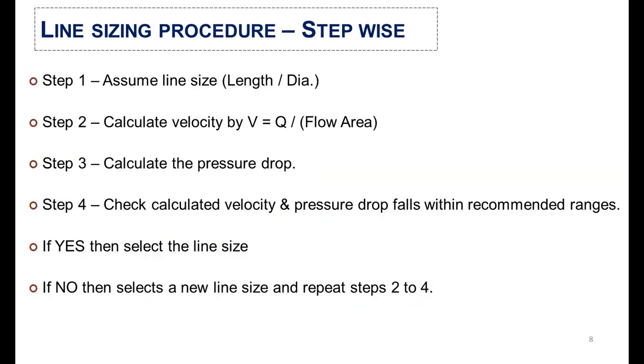The main steps for the line sizing procedure are as follows. In the first step, you assume the line size — the length and the diameter. In the second step, you calculate the velocity. In the third step, you calculate the pressure drop. In the fourth step, you check whether the velocity and pressure drop comply with recommended ranges. If they comply, your selected line size is acceptable. If not, you repeat steps two to four.